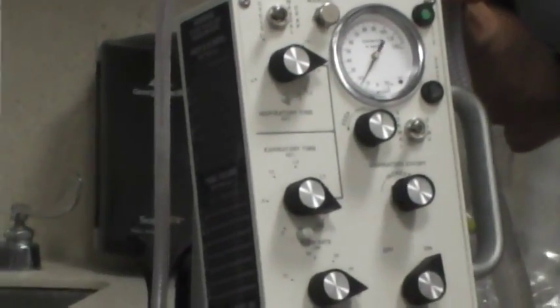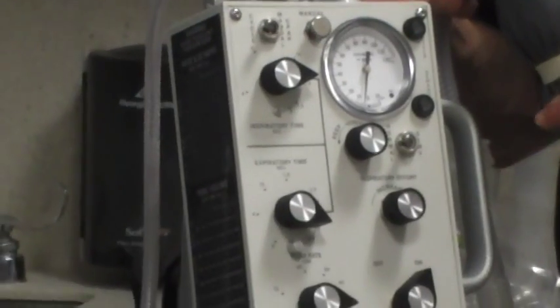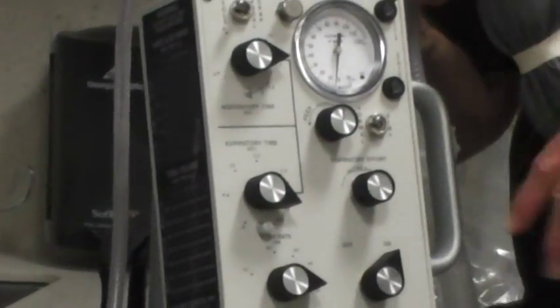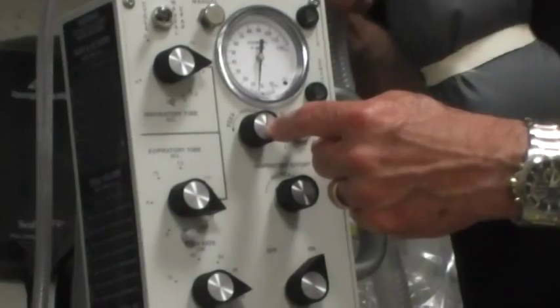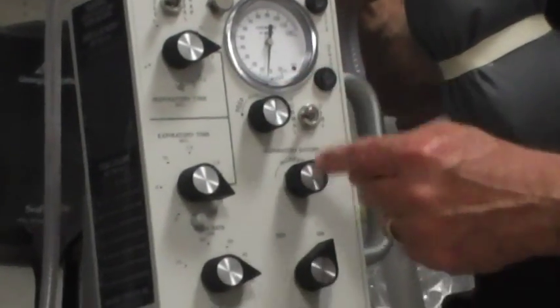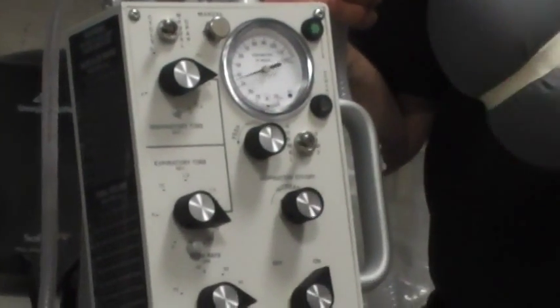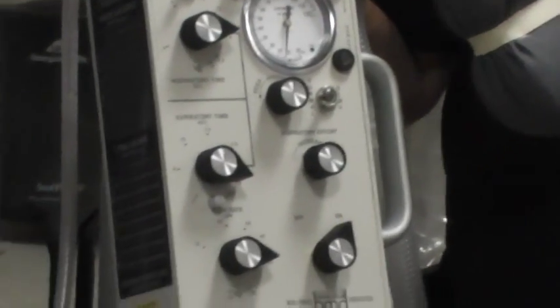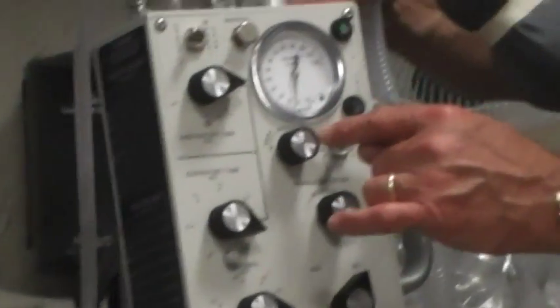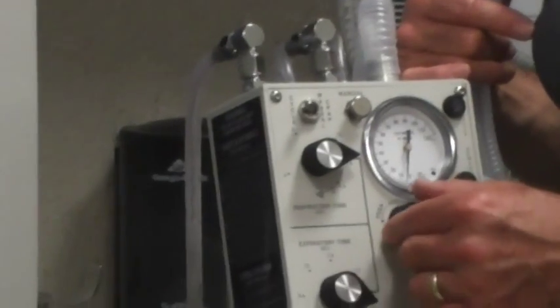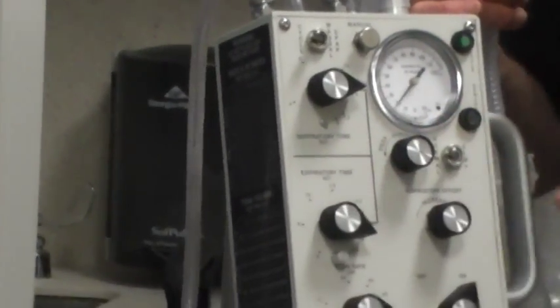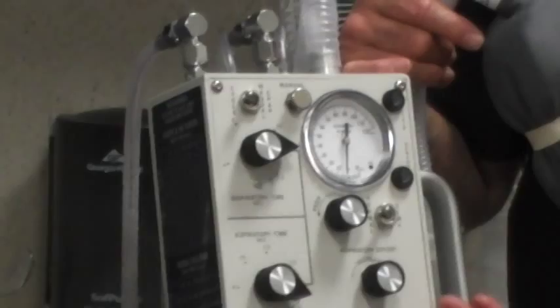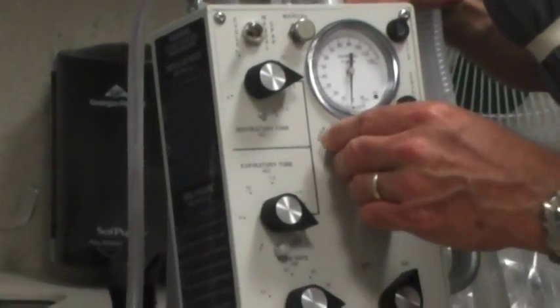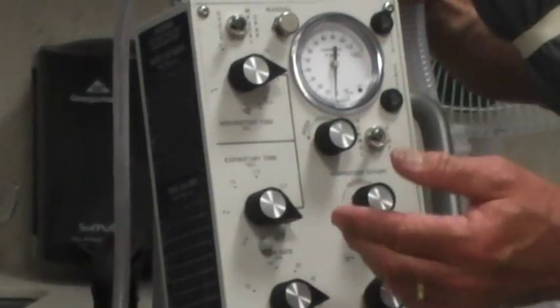So now, the last thing to really talk about, oh, two things. If you change your PEEP, you always have to reset your sensitivity. It doesn't auto-correct or auto-compensate for PEEP. If you go down on your PEEP, that's pretty easy because you're going to auto-cycle. If you go up on your PEEP, that's where you might forget and you don't know.